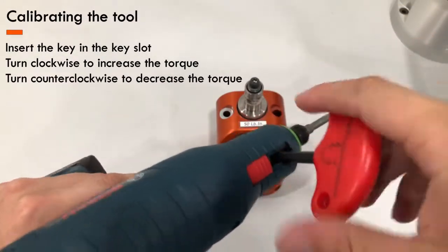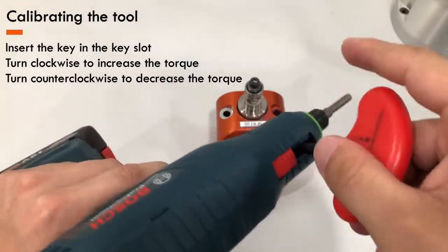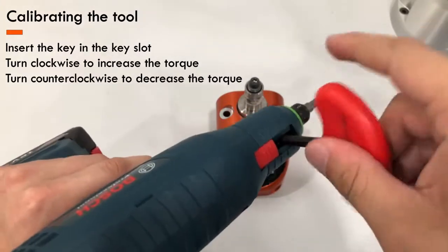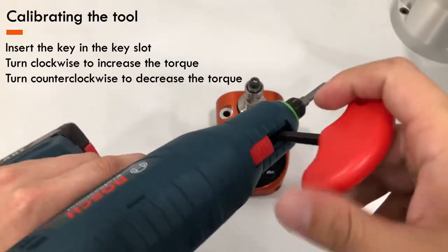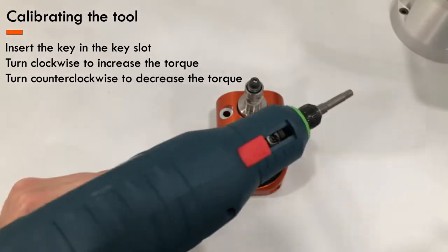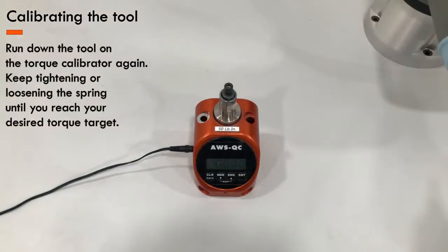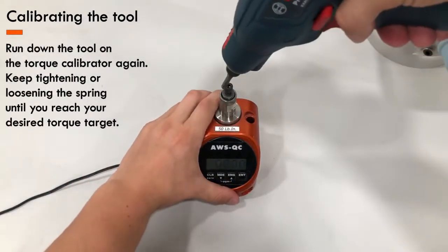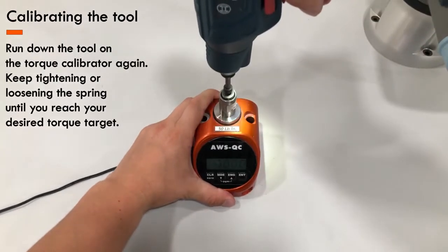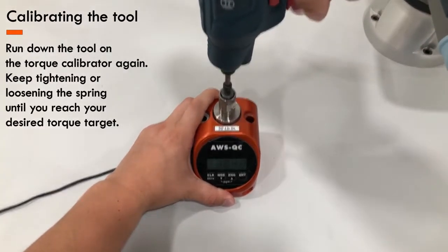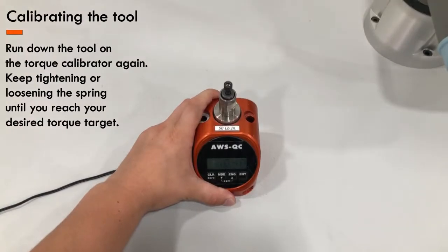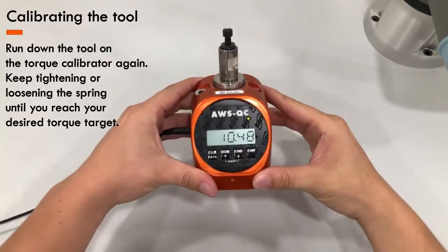In this case, I am trying to reach a 10.5 inch-pounds torque target. Since my tool is hitting a torque of 8.65, I am going to tighten the spring and turn clockwise to increase the torque. Run down the tool on the torque calibrator again. Keep tightening or loosening until you reach your desired torque target.